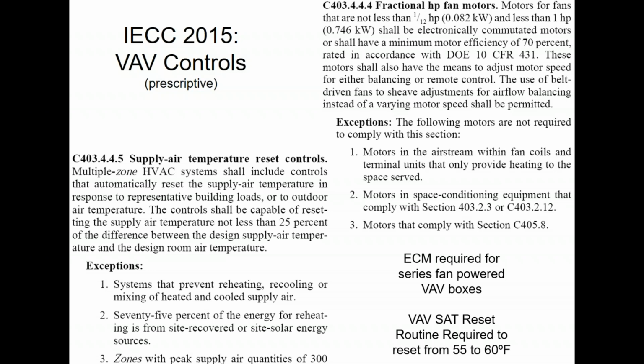You typically reset that based on the average zone temperature as compared to the average cooling set point for those zones. So if on average the zones are all pretty happy, if you will, or overcooled, if you want to think of it that way, we start tweaking the supply air set point up from 55 to 56 to 58 to whatever it needs to be. So that is a requirement of the code as well. That is required on both DDC and non-DDC systems. So if you have non-DDC, you're probably going to do it based on outdoor air temperature. If you have DDC, you're going to do it based on indoor zone temperature. But you do have to have both supply air reset and static pressure reset.